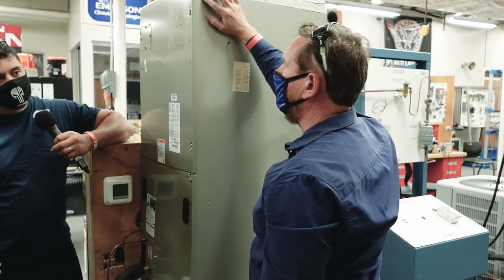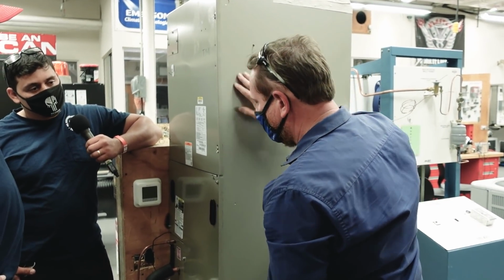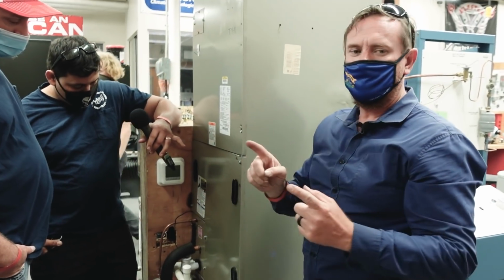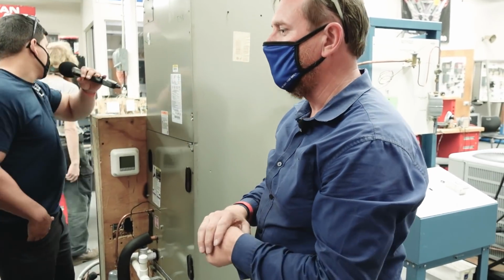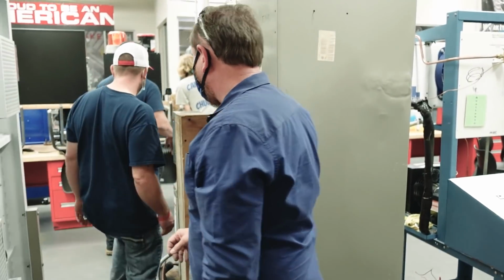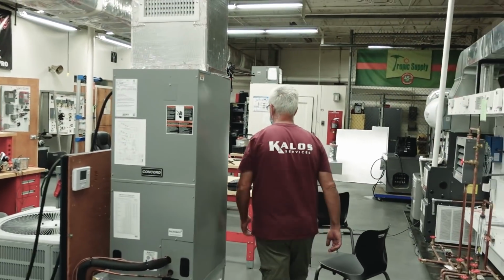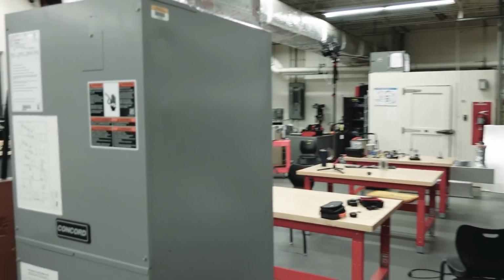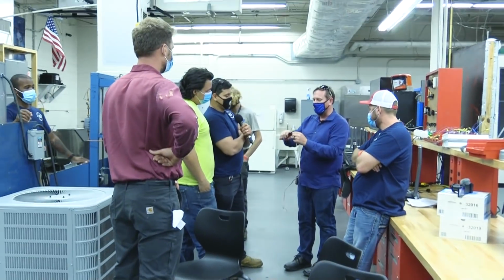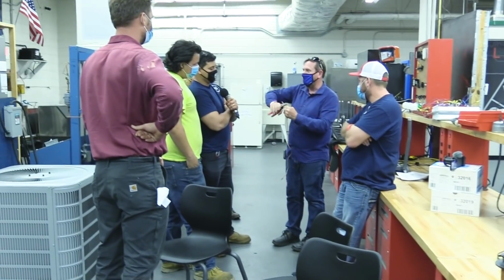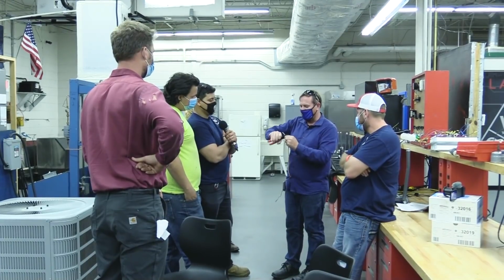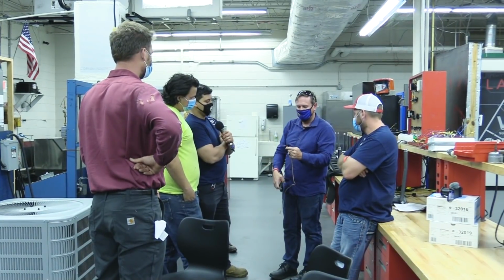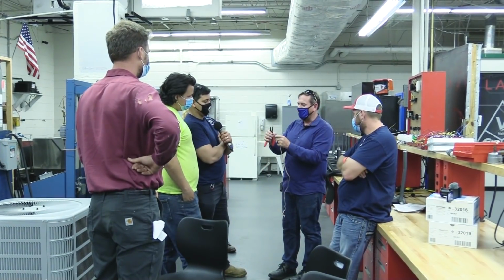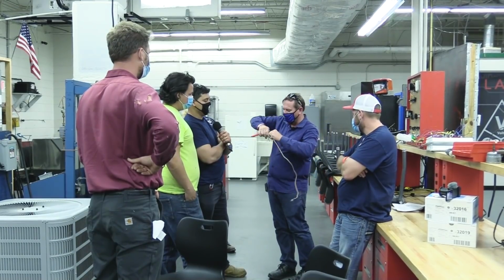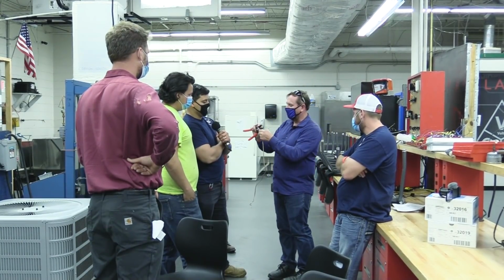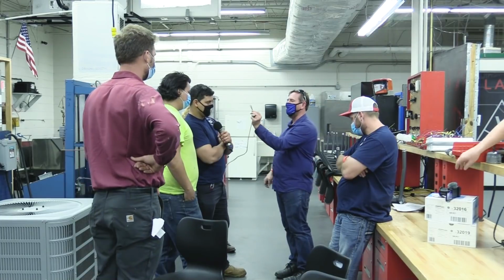Also, stripping this low voltage wire. Do we have a piece of low voltage thermostat wire and a wire stripper? When people strip thermostat wire, they notoriously do this. We have some with the outer coating still on. This is what a lot of people do: they'll take the wire like this, strip the outer coating, and then do this. Well, what they don't see is what's happening right here. So we're going to pull this out. Now look at all those little nicks I left on there.